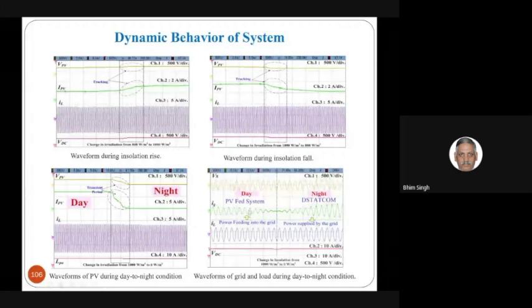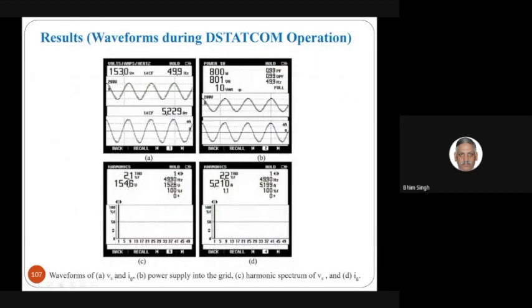So in the daytime, of course, it is feeding power to the grid at unity power factor. But in the night time, it works as a DSTATCOM or active filter, and the grid current is still maintained sinusoidal and in phase with the voltage, even though the power is coming from the grid to meet the load requirement. Your load remains constant. In the daytime, the power for feeding the load comes from the solar generation, but in the night you don't have generation, yet you still need power for the local load. That is supplied from the grid, but the harmonics and reactive power are supplied by this voltage source converter, and it provides sinusoidal current. You can clearly see the THD of the grid current is still 2.2% when the voltage also has THD of 2.1%, and it operates almost at unity power factor.